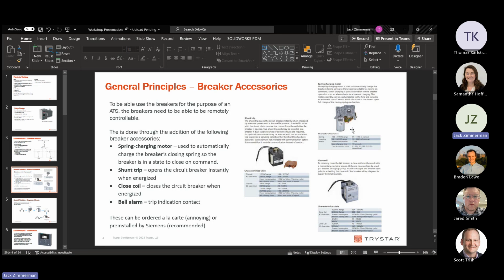So the spring charging motor makes it so you don't have to sit there and pump up the breaker every time you want to actuate it, which is very important for remotely switching the breaker. The shunt trip is another accessory within the breaker that opens the breaker instantly when you energize it with the rated voltage for that shunt trip. We do have shunt trips that go in a lot of our units. So that's not too uncommon, but typically the way we're using shunt trips is you have some kind of control signal that's coming into it that's telling it to open under some kind of fault condition. We're not doing it so much to actually change sources.